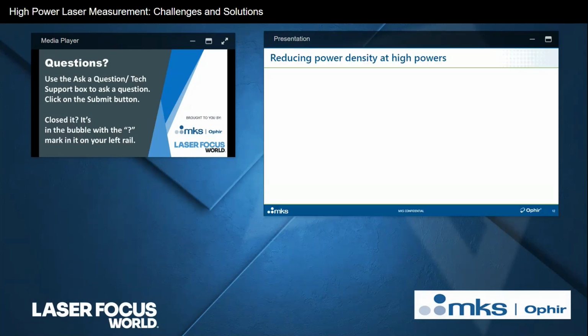As we just explained, with high power beams, the damage threshold is significantly lower than it is for the same absorber at lower powers. So for high power sensors, which is what we're talking about, where this is going to be that much more of a concern, we want to keep the power density as low as we can, which we do by this trick, whereby we enlarge the beam before it actually reaches the absorber.